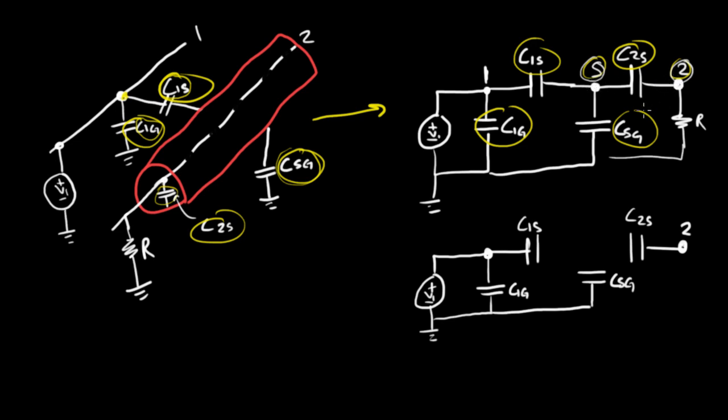And this is very bad because whatever noise voltage that the shield picks up can be capacitively coupled to wire two, which eliminates the reason for having a shield in the first place as far as capacitive coupling is concerned.